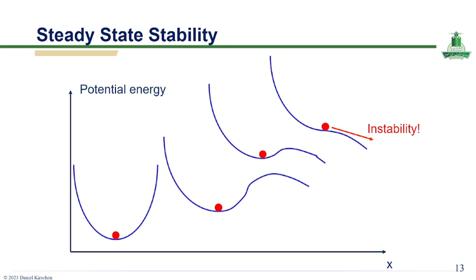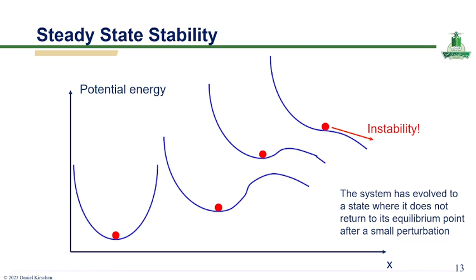In terms of the potential energy concept, a stable operating point corresponds to a local minimum where the system naturally tends to remain. However, if system conditions change significantly, the operating point may shift to a region where this restoring property is lost. Even a small perturbation can then prevent the system from returning to equilibrium, indicating instability. This means the system has evolved to a condition where it can no longer maintain steady state stability, and its normal operation is no longer secure.